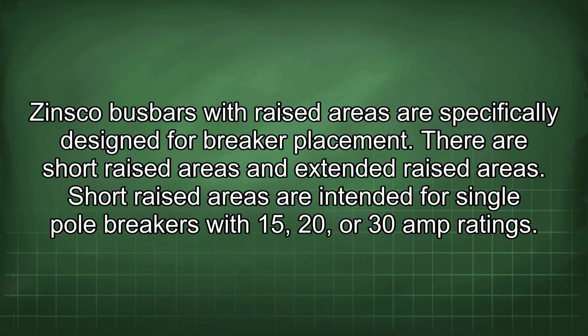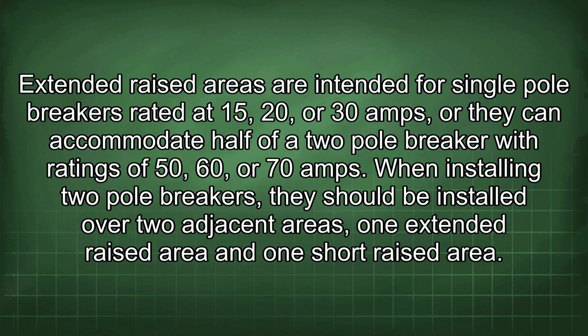Zinsco busbars with raised areas are specifically designed for breaker placement. There are short raised areas and extended raised areas. Short raised areas are intended for single pole breakers with 15, 20, or 30 amp ratings. Extended raised areas are intended for single pole breakers rated at 15, 20, or 30 amps, or they can accommodate half of a two-pole breaker with ratings of 50, 60, or 70 amps.